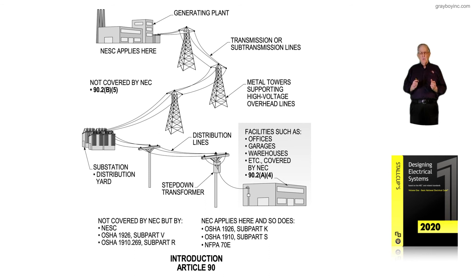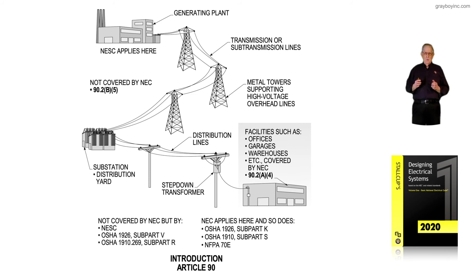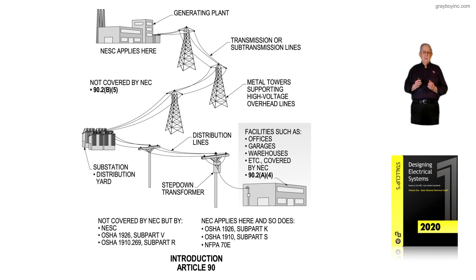Three main standards, along with others, are applicable on the load side. First, the NEC. Then OSHA 1926 subpart K, which covers all the wiring inside the building, the wiring to the equipment, and the wiring of the equipment. Once the equipment has been wired and accepted by the facility owner and approved by the authority having jurisdiction — in this case, electrical by subpart K — then OSHA 1910 subpart S takes over to maintain the equipment.